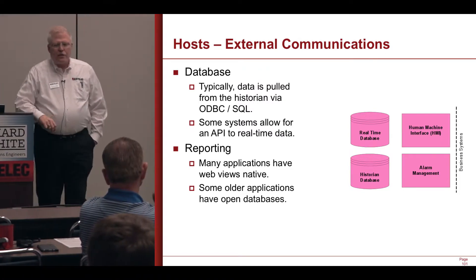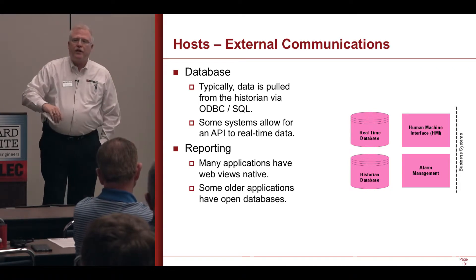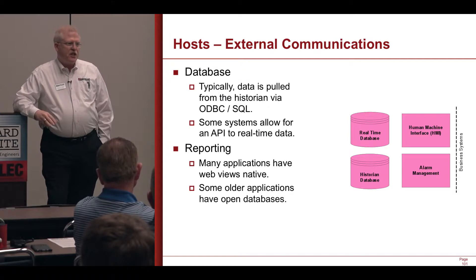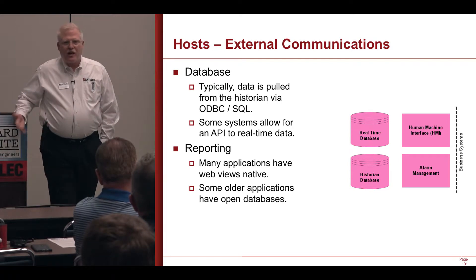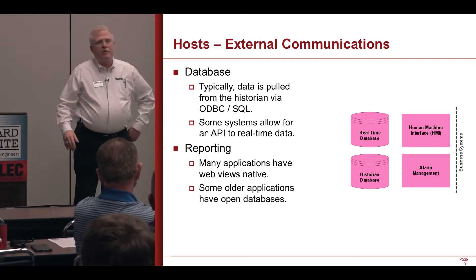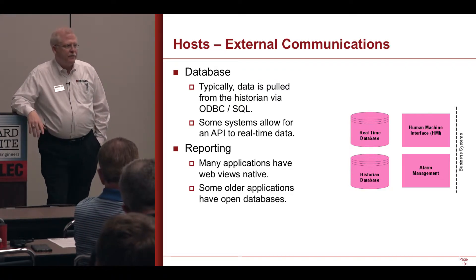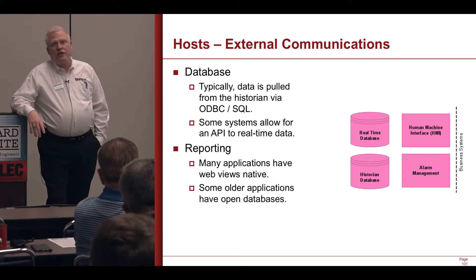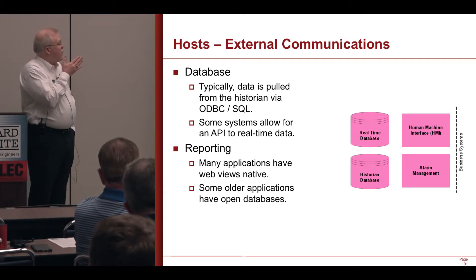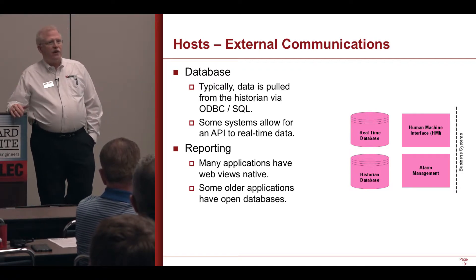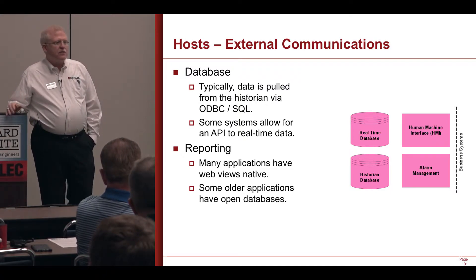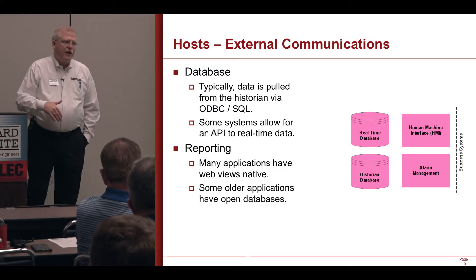Almost all SCADA systems have proprietary databases — both the real-time database and the historian — because these are optimized as a very flat data structure: a list of points, the last value I got, that's all. There's not a lot of relational tables or complex indexing; they're optimized for speed. The real-time database ensures I get data in a second or less when I ask for it. Some historians are SQL-based, but by and large they're proprietary as well. ClearSCADA, for example, has a SQL interface but it's still a proprietary data structure — they support a simple subset of SQL queries and expose their database as SQL.